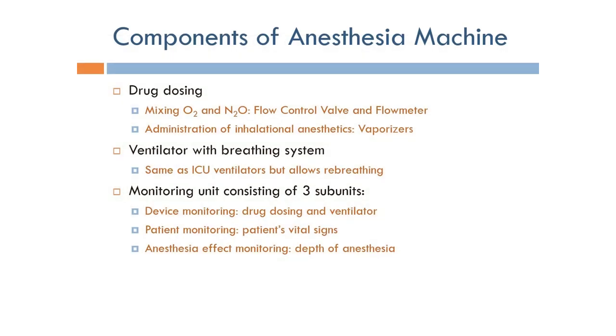The main components of the anesthesia machine are: first, the drug dosing part, which is responsible for mixing oxygen and nitrous oxide using flow-controlled valves and flow meters, and for the administration of inhalation anesthetics, which is taken care of by vaporizers.